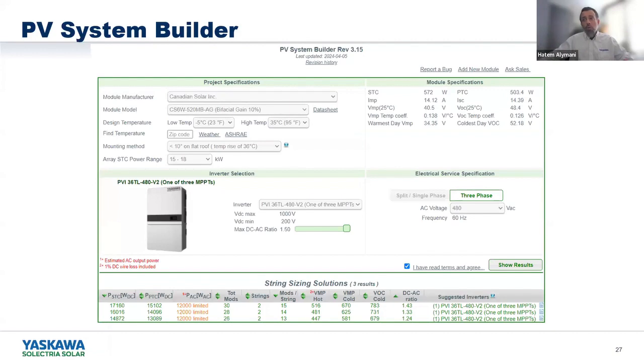So it depends on the inverter, and it depends on the designer. If you see a warning here, this is not bad. This is only telling you that the DC to AC ratio is higher. Of course, the inverter is always going to clip at this value. So at the MPPT, I would say it will clip at 12. My apologies. It will clip at 12 kilowatt, but per MPPT. So for 3 MPPTs, 12 and 12 and 12, that will be the complete 36 kilowatt.